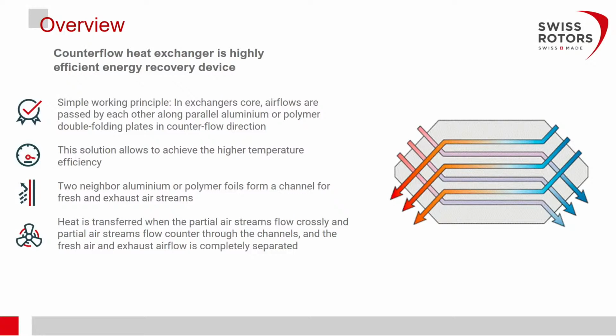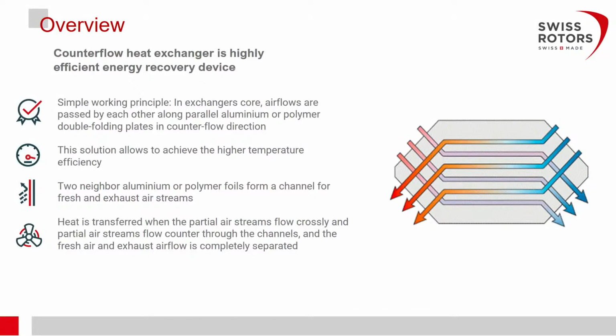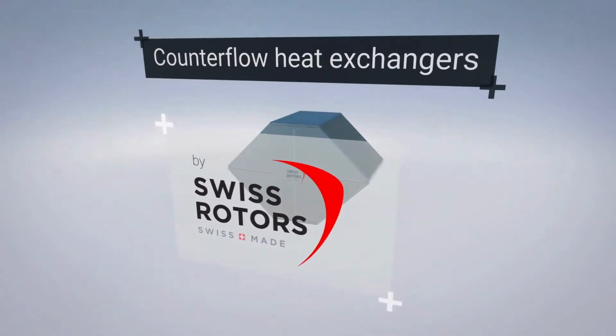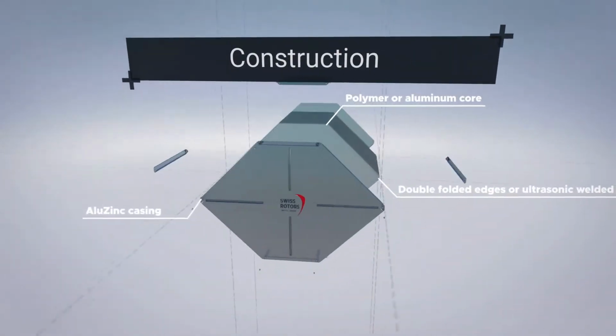Instead of aluminum core plates, we can also have high impact polystyrene core plates. The heat is transferred when the partial airstream flows crossly and the partial airstream flows counter through the channels. And then the fresh air and the exhaust air are completely separated, exchanging the parameters through the aluminum plates. So, a short video on how it works and how it is built. So you can observe this Counterflow. There are external parts and then the internal core. And this is how the air goes through, and then the channels, which are parallel in different locations.